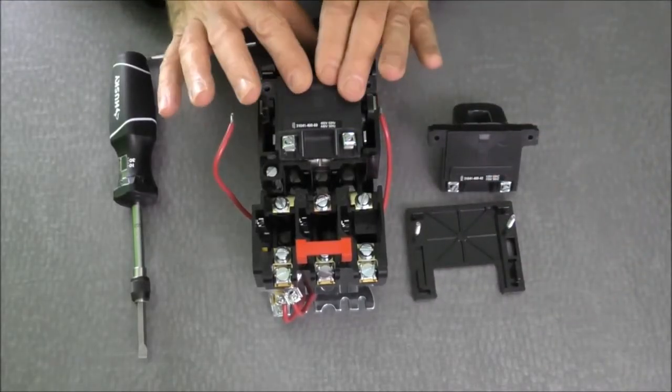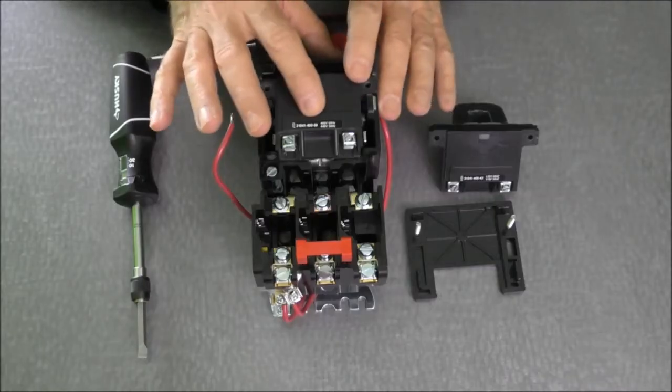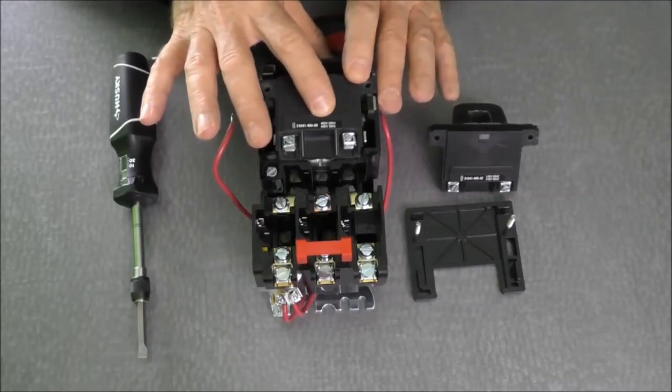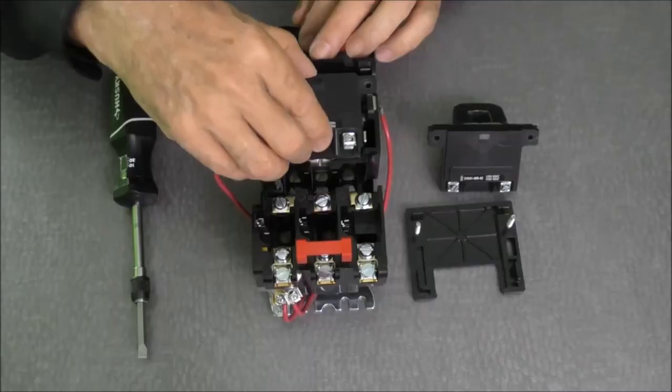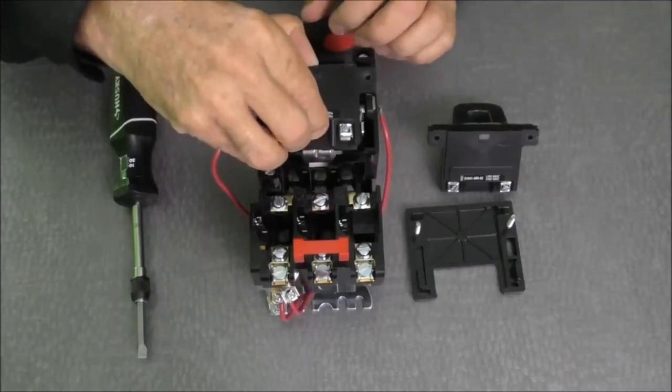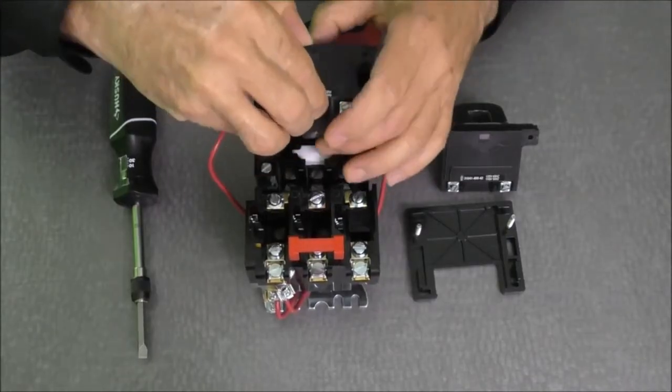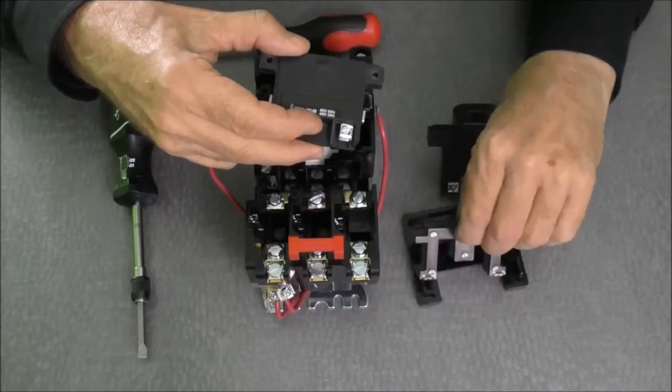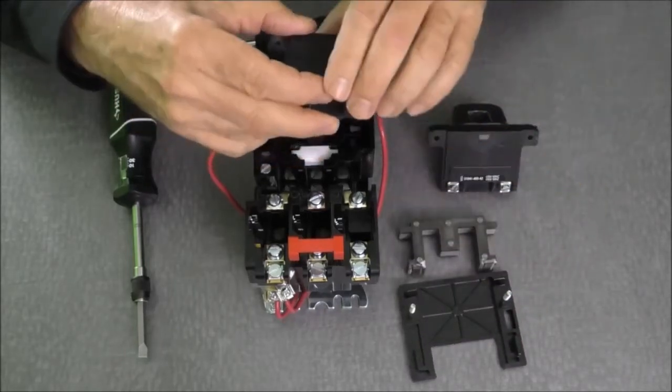Once that's accomplished, we have the coil exposed. This particular coil happens to be rated for 480 volt 60 hertz, 440 volts 50 hertz. My next step will be to pull the coil straight up, and when I pull that coil straight up, I get the magnet and I get the armature that comes out with the coil.